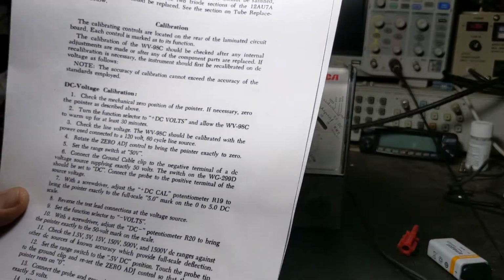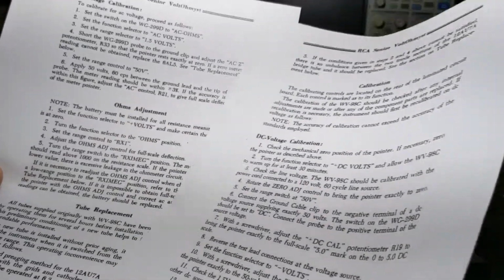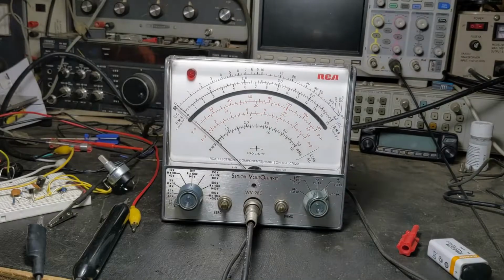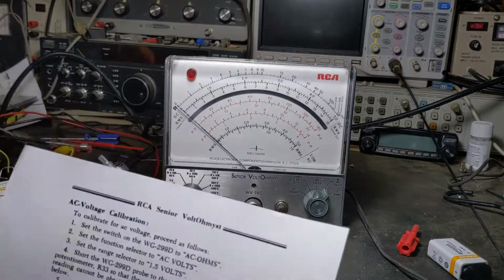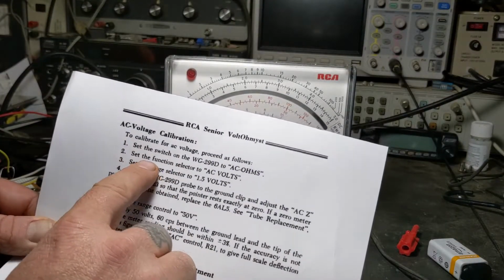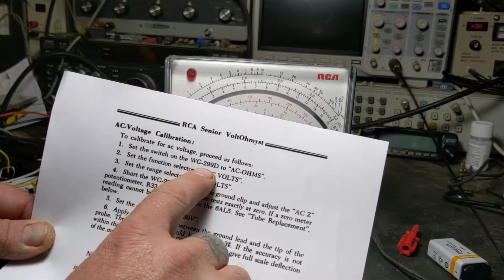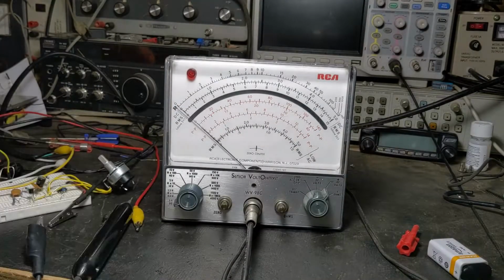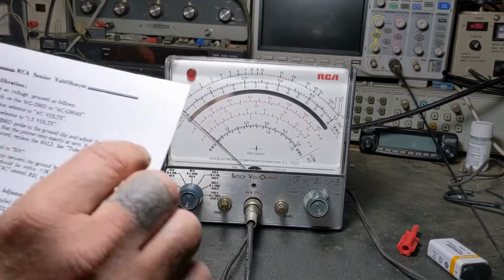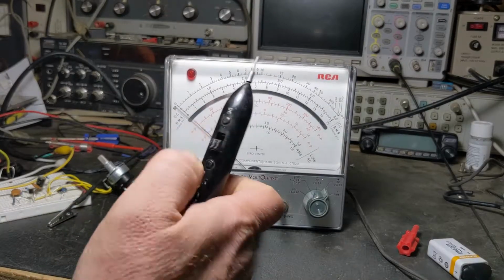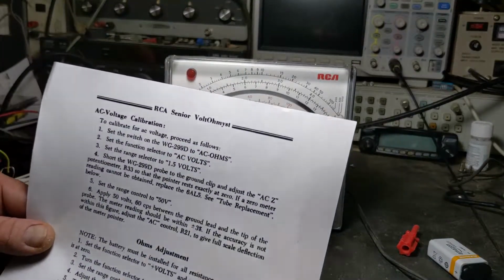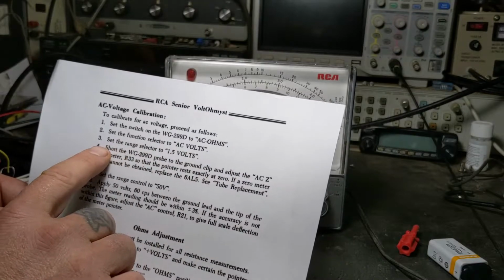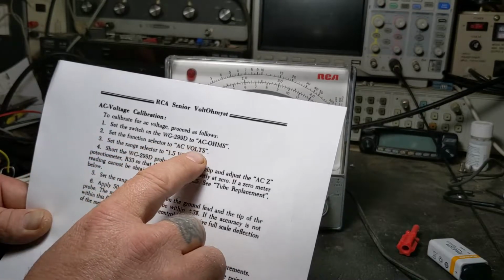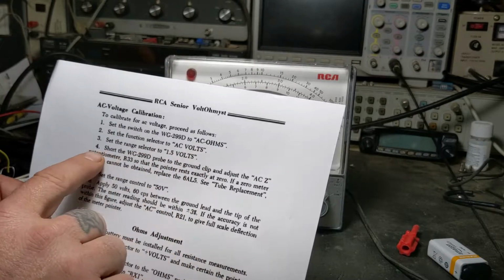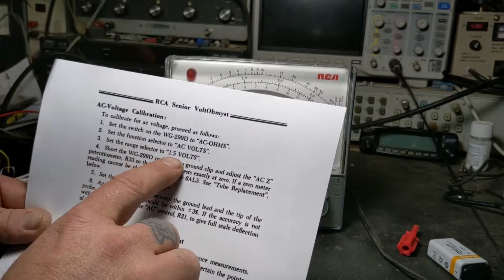Now, so we've got that done. And we're on here now to the AC calibration. Set the switch on the WG299D. If you have the actual probe that came with it, it'll be an RCA, WG299D to AC, and that'll be flipping the switch back here to AC. Set the function selector to AC volts. Set the range selector to 1.5.